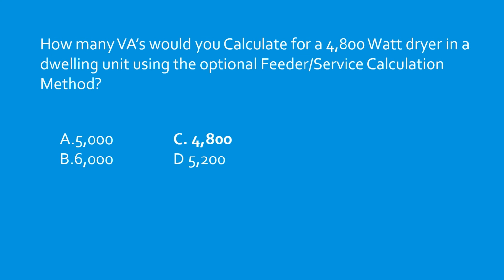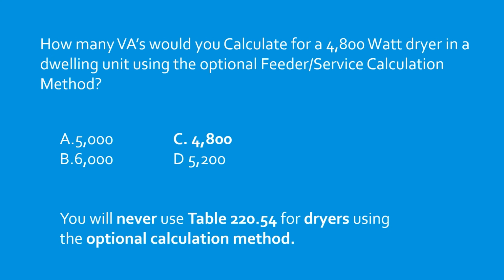How many VAs, recapping, would you use for a 4800 watt dryer? We just read that you're going to use the nameplate, so you're going to select 4800. You will never use Table 220.54 for dryers when using the optional calculation method. You have to remember that. So if they ask for 11 dryers and they're 4800 watts apiece, you just total them all together and that's your answer.